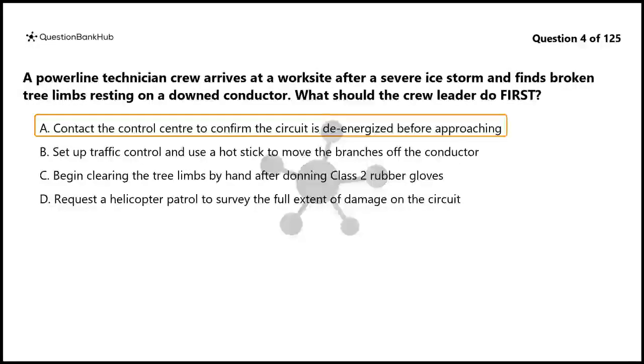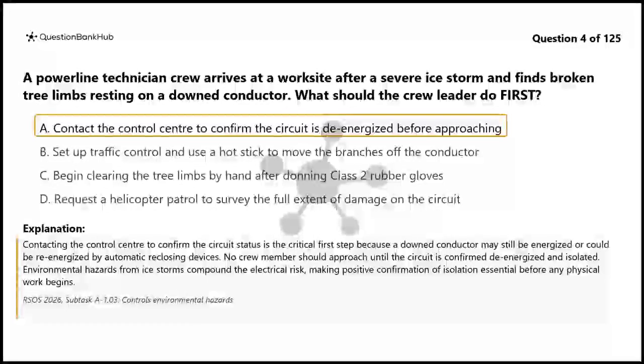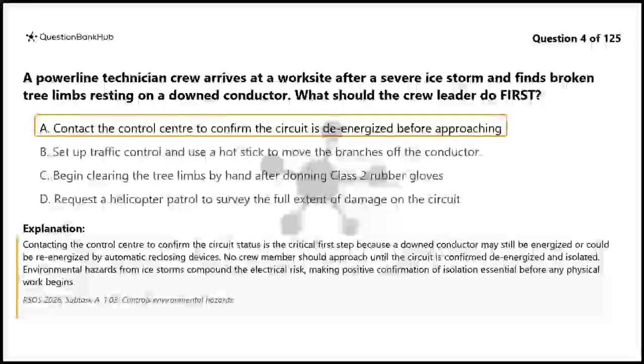The correct answer is A. Contacting the control center to confirm the circuit status is the critical first step because a downed conductor may still be energized or could be re-energized by automatic reclosing devices. No crew member should approach until the circuit is confirmed de-energized and isolated. Environmental hazards from ice storms compound the electrical risk, making positive confirmation of isolation essential before any physical work begins.